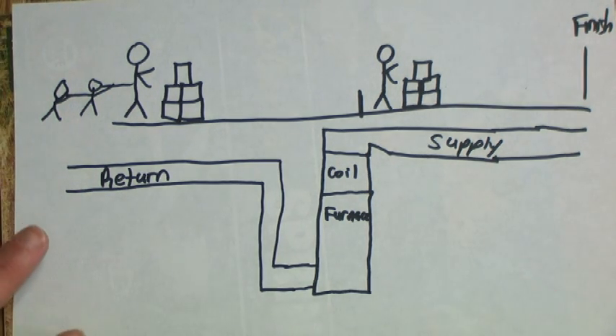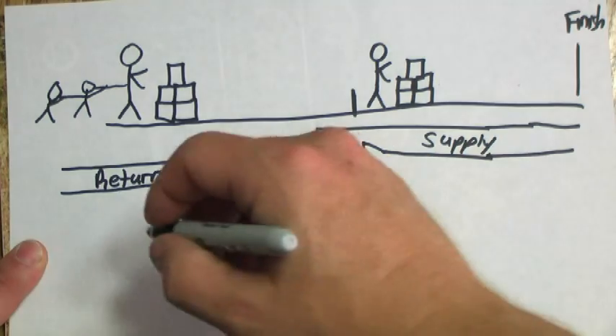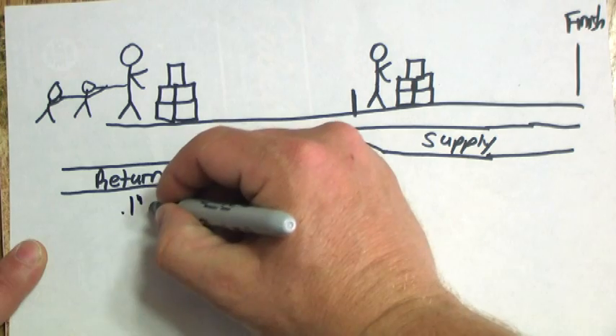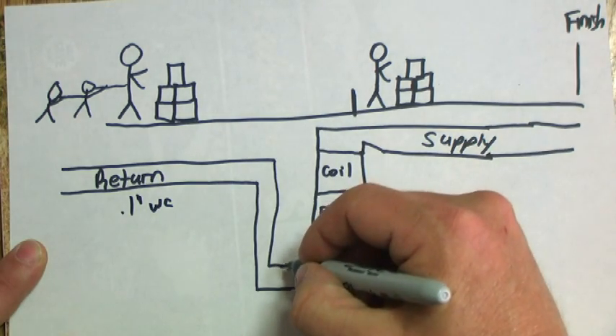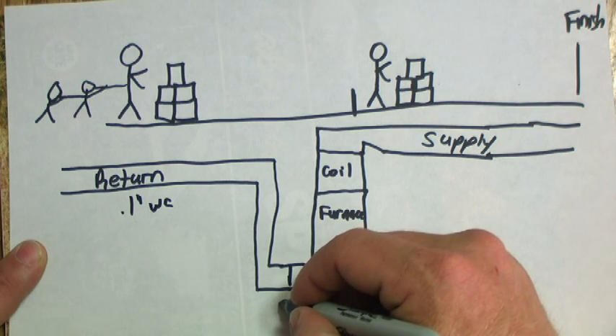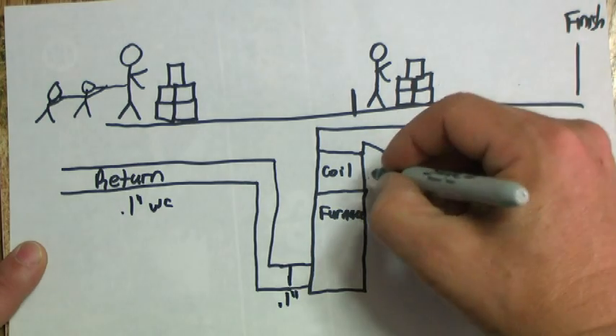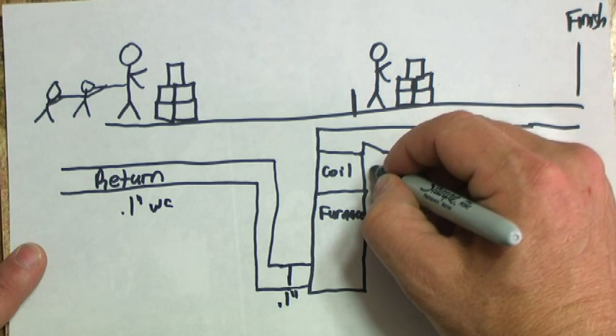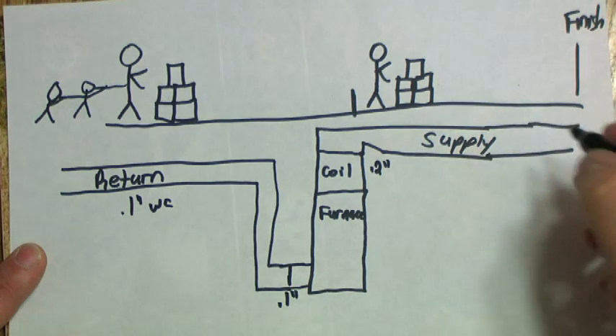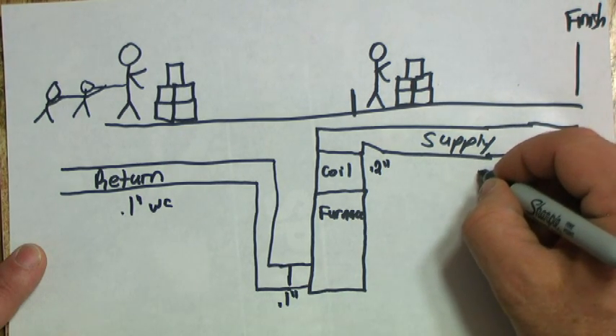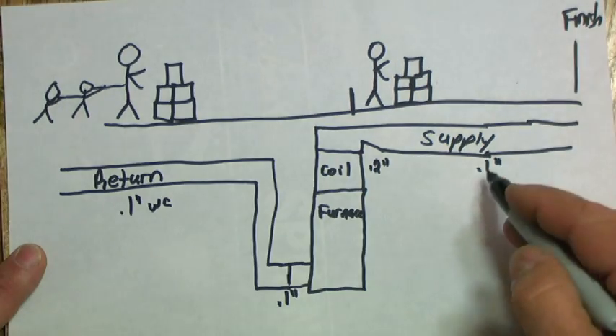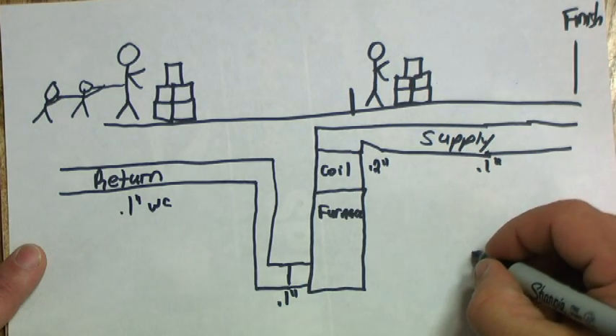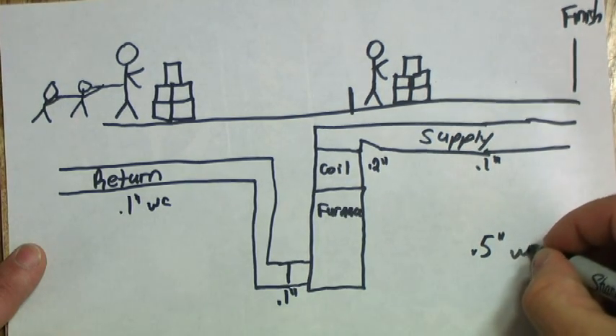So what we want, ideally you would like to try to get like a 0.1 inch water column on your return. You have a filter here. You want a 0.1 inch on it. Then you have a coil, we'll just say 0.2 inch on your coil. Then your supply, we want another 0.1 inch. If you add all these together, two, three, four, five, that gives me my 0.5 inches water column.